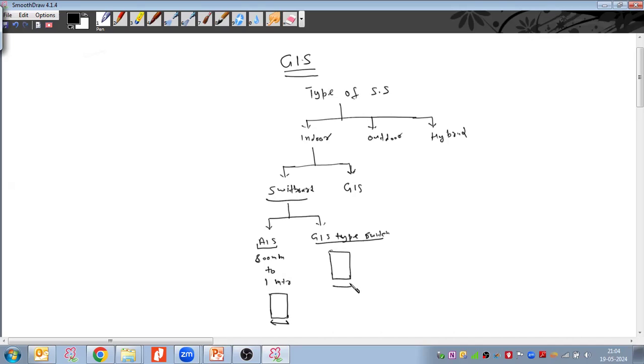The panel width is less compared to the AIS switchboard. It could be in the range of 400 to 600 millimeter, max 600 millimeter. It could vary from manufacturer to manufacturer. This is up to 33 kilovolt. But when the voltage level increases beyond 33 kilovolt, we go with the GIS module type substations. This is for the indoor, and then we discussed outdoor, which is called the AIS.